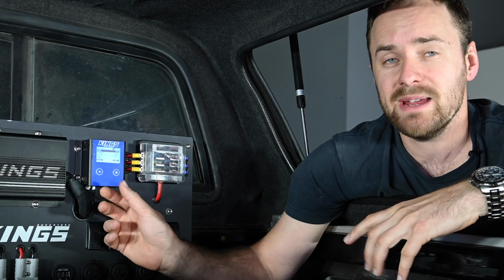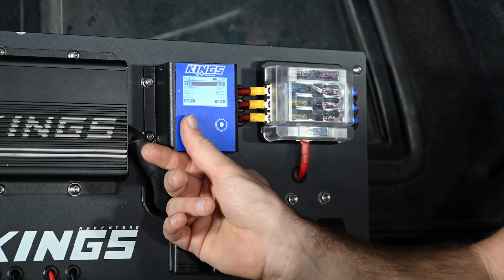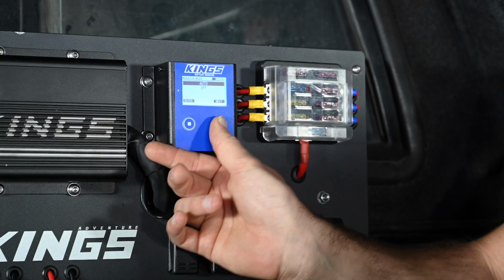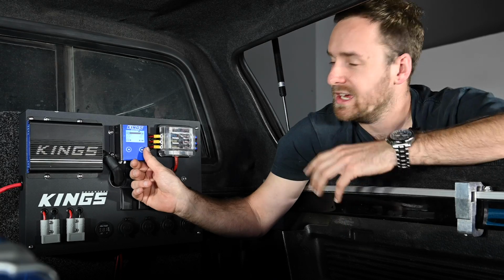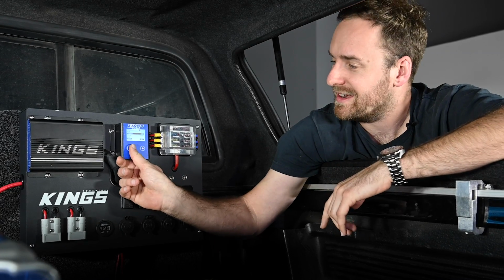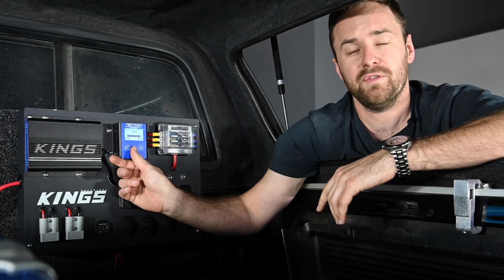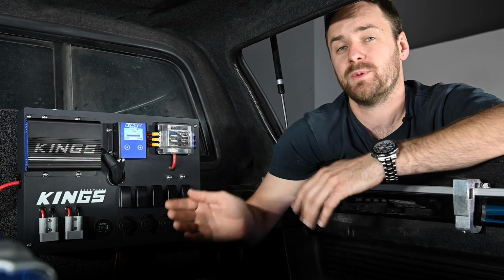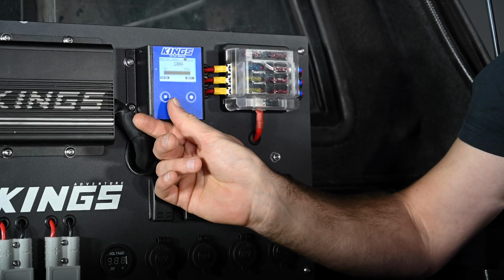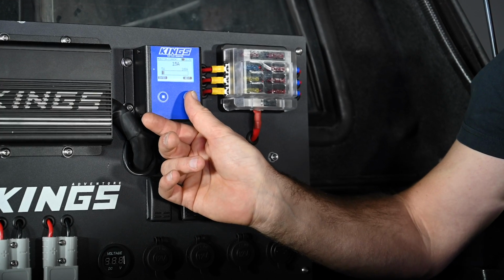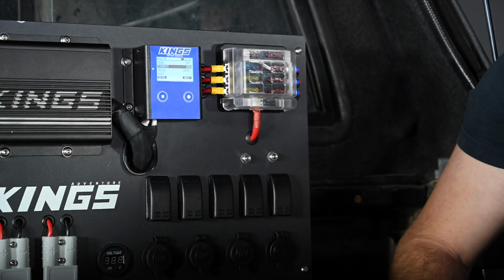The first menu item here is your mode, which does the same thing as long pressing the left-hand button on the home screen. It selects auto or off. After that, you've got current. Now that is your overcurrent cutoff, and it can be selected anywhere from 5 up to 100 amps. So if you want your system to shut down if it reaches 20 amps or higher, simply select 20 amps.